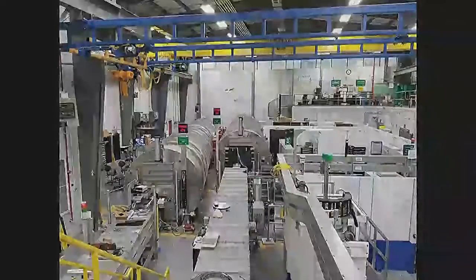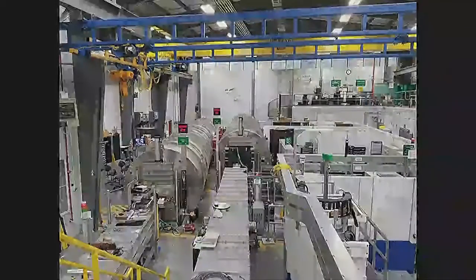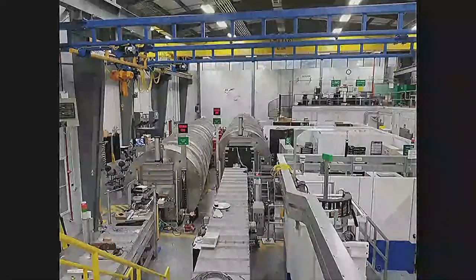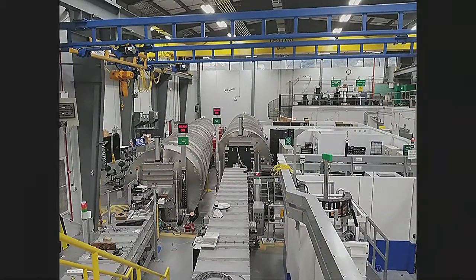So this is an aerial view of the SANS instruments at HFIR. The neutron guide is in this area here. The velocity selector is somewhere around here. Your sample goes in a sample holder right there, and then this is a big vacuum chamber that holds your detector at the end. The neat thing about this is they actually have two detectors, one that's close to the sample right up here. So you actually get wide angle neutrons that are scattered off in addition to the small angle neutrons.